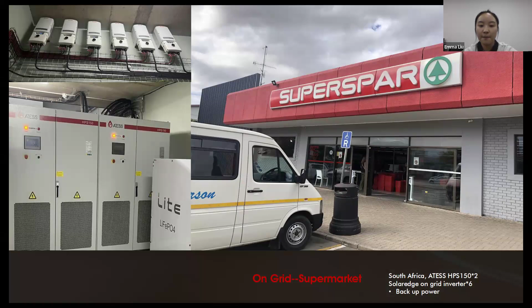In some cases, customers already have a PV inverter system installed, and as electricity demand grows, they need to expand the old system. Our inverters, whether HPS or PCS, can be connected to the original PV inverters as an AC coupled extension. This is one of the AC coupled sites where the ATESS inverters are connected to 6 PV inverters to power a supermarket in South Africa.